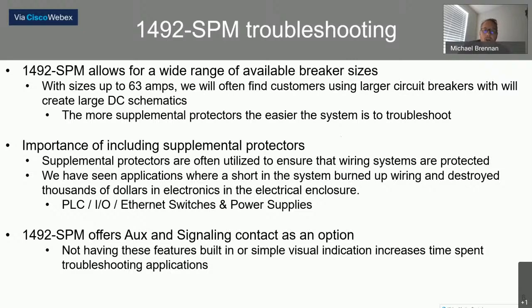What you have to realize is the more supplemental protectors you use, the easier the system would be to troubleshoot. Because the smaller each of those circuits is, the smaller the number of devices that you have to troubleshoot for that specific circuit if there was a fault, whether that fault be a short or just a failure of a device. Often we'll see proximity switches that get crushed and cause shorts in DC schematics. If you have a very large circuit that feeds quite a few sensors, then this can be very difficult to go through and individually troubleshoot.